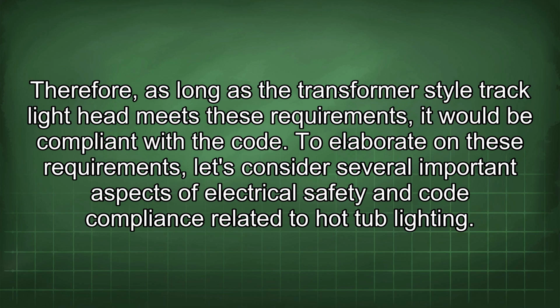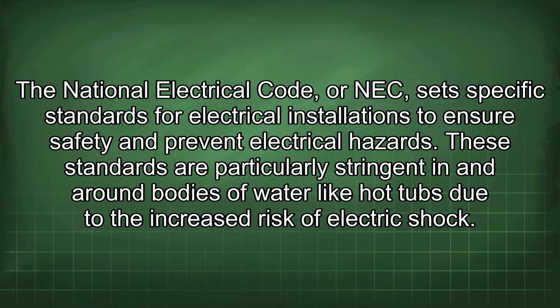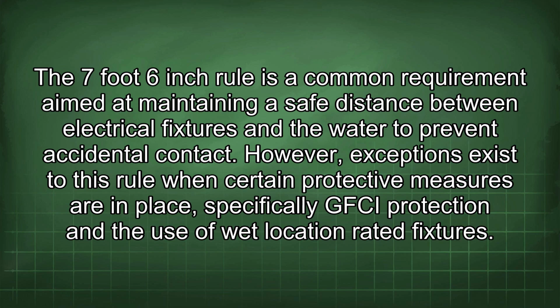To elaborate on these requirements, let's consider several important aspects of electrical safety and code compliance related to hot tub lighting. The National Electrical Code, or NEC, sets specific standards for electrical installations to ensure safety and prevent electrical hazards. These standards are particularly stringent in and around bodies of water like hot tubs due to the increased risk of electric shock. The 7 foot 6 inch rule is a common requirement aimed at maintaining a safe distance between electrical fixtures and the water to prevent accidental contact.